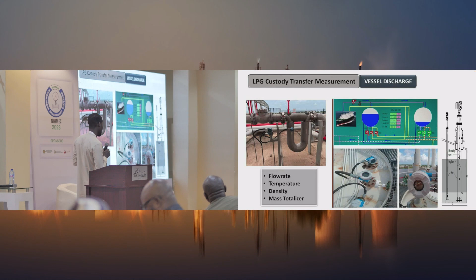You need to know the density of your vapor phase. To do this, we actually use a formula and run calculations day and night. You have to take into account your liquid temperature, your pressure, and your gas temperature, then use that in a formula to get your gas density. Multiply that by the remaining space and you get your vapor mass.